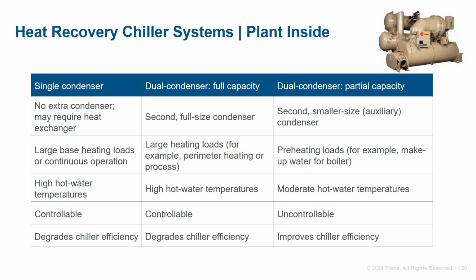This table shows some trade-offs for each type of condenser. As an example, a second full-sized condenser can provide higher fluid temperatures than the smaller auxiliary condenser. That's why it's important to have as much understanding around what the load profile looks like and the required fluid temperature so the right piece of equipment can be selected. Depending on the coincident load magnitude, duration, and staging planned, these all provide options to reuse heat that would otherwise be rejected at varying levels of additional cost.